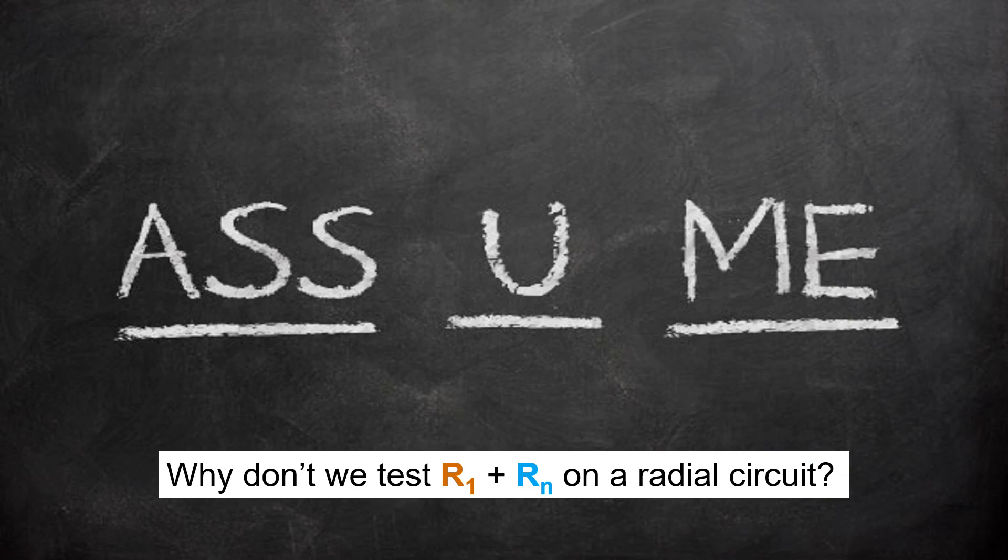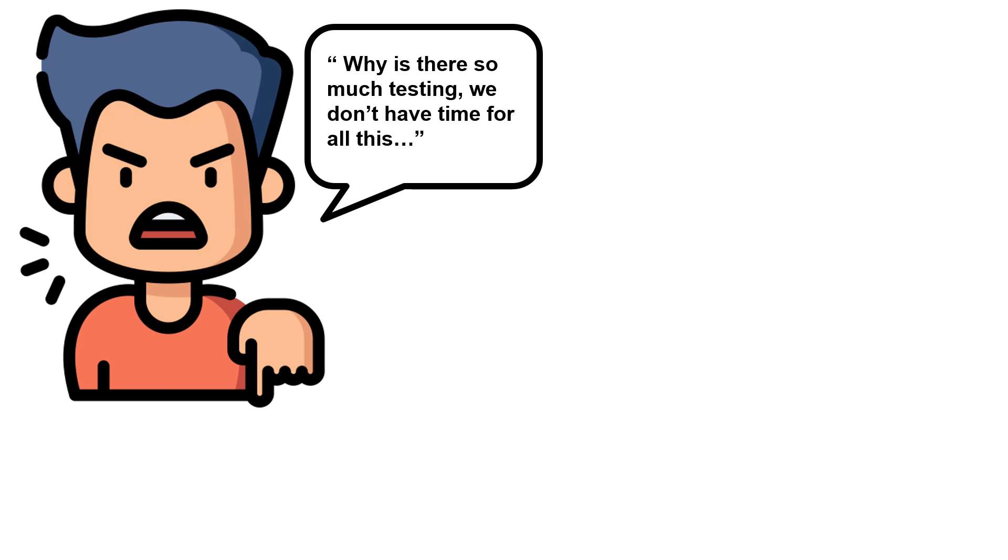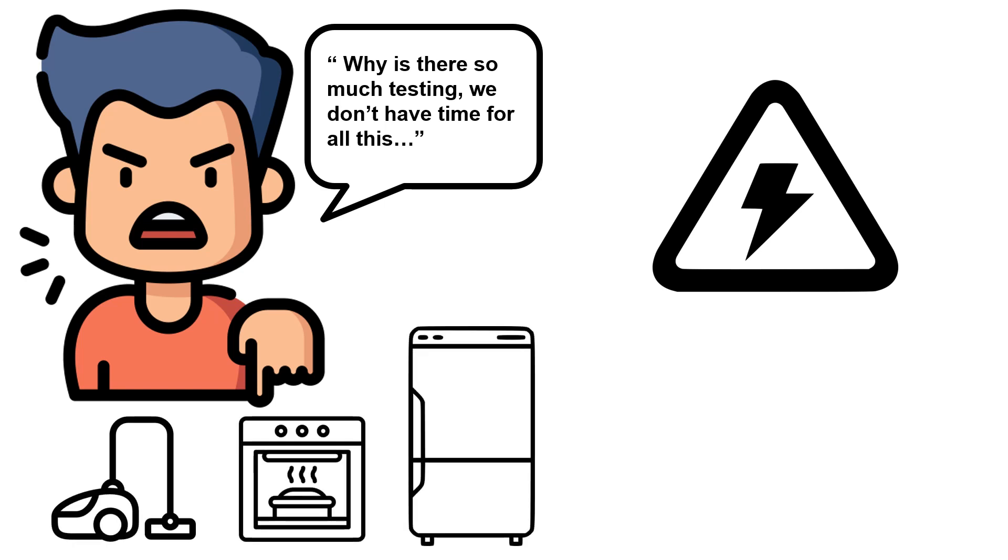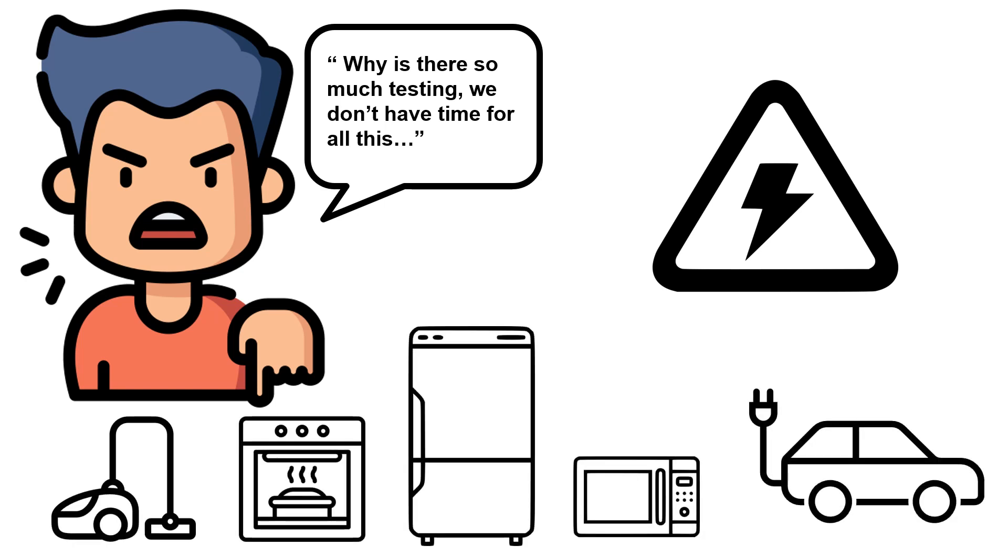Personally, I do not agree with assuming that R1 plus Rn on radial circuits complies just because the R1 plus R2 did. We all know what they say about assumption and if you do not test R1 plus Rn on every circuit, then how would you prove beyond all reasonable doubt that there was no fault on the neutral conductor? And so many reasons why, but apparently, and I don't know how true this is, but the logic behind not doing the test is that people already complain about how much testing is required and simply won't do the test. Or the worst thing that can happen is that the appliances just won't work, which we all know just isn't true.